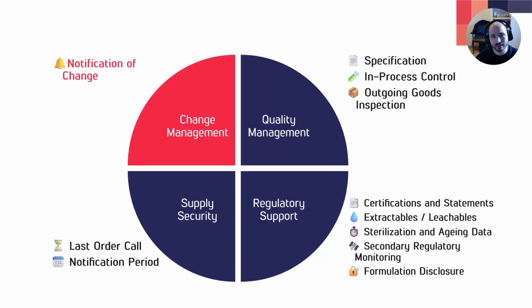Then, why do I need this as a medical device manufacturer? I, of course, need to look at the risk management that I currently have with my device and see if the change has any impact. It doesn't mean that if you get a change from your material supplier, you always need to revalidate. Sometimes you do. Depending on your risk class, you do a lot. And sometimes it's just a change where the mechanical properties and the color might be off a little, but we can accept it. And we do not need to revalidate or sample each and every part.